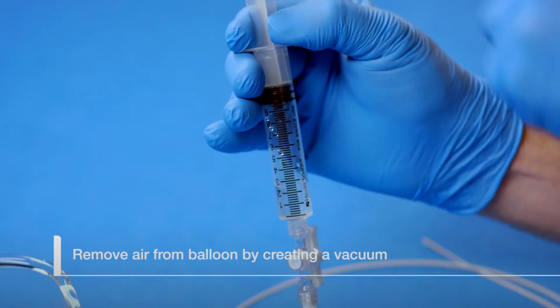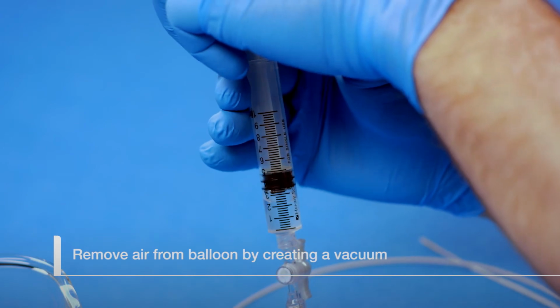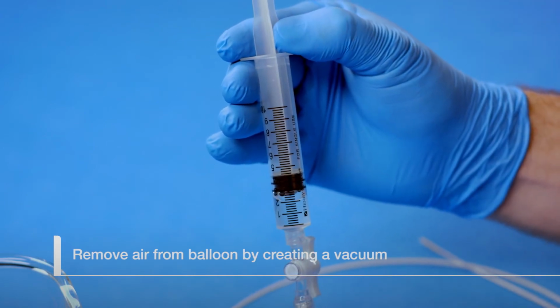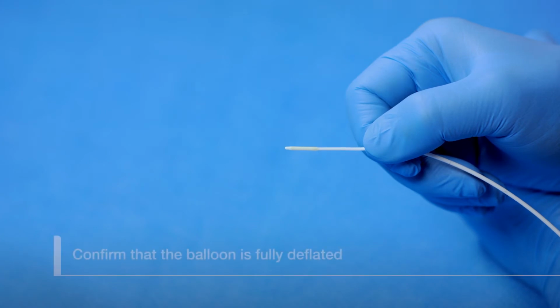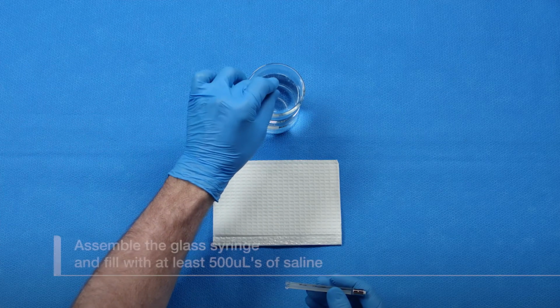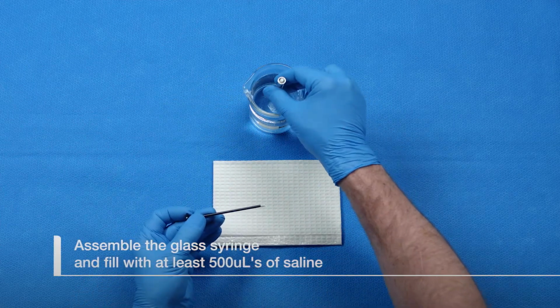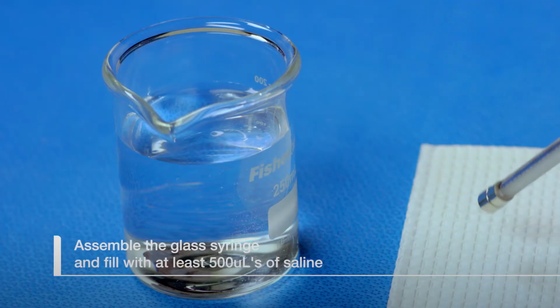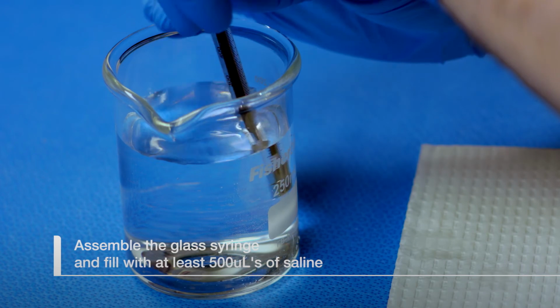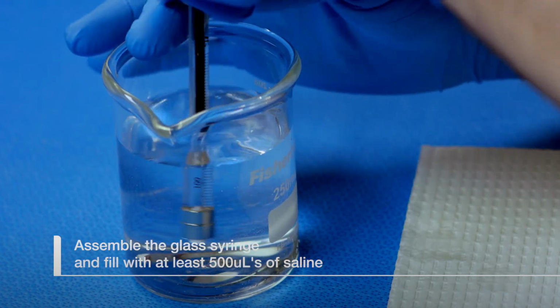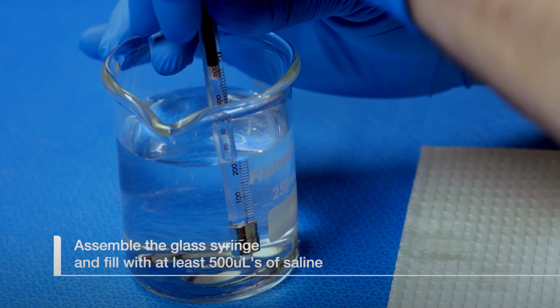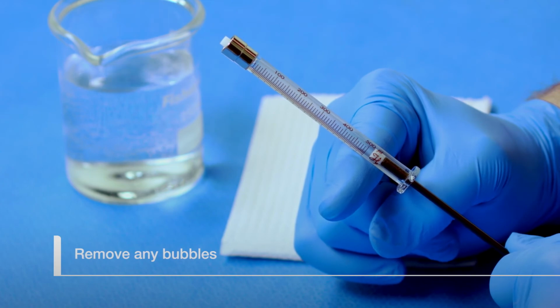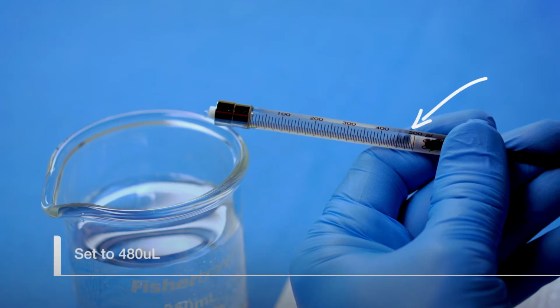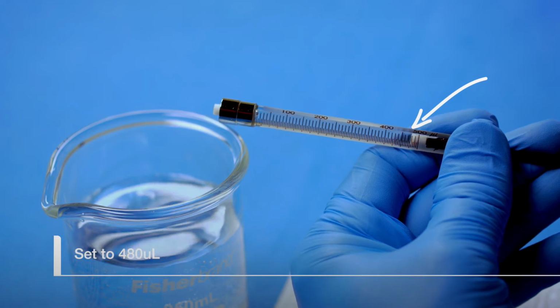While keeping the syringe with the plunger up, slowly release the plunger until the vacuum is no longer present. Visually confirm that the balloon is fully deflated after this step and set aside with syringe still attached. Using sterile saline, wet the plunger for the glass syringe from the airway sizing kit and completely insert it into the 500 microliter glass syringe and fill with at least 500 microliters sterile saline. Remove any air bubbles from the syringe. Set the syringe to the 480 microliter mark and set aside.